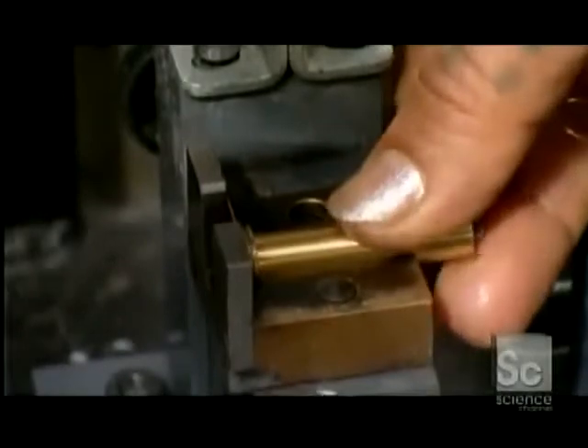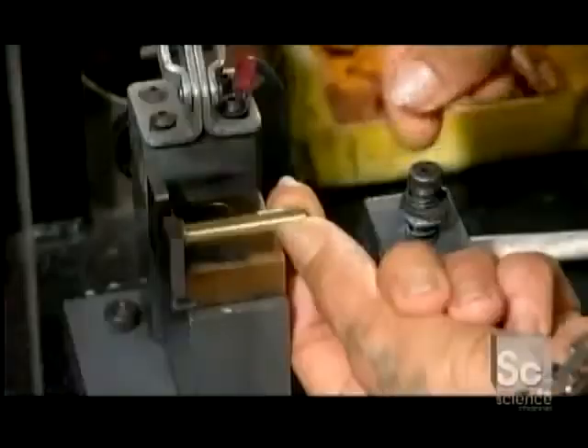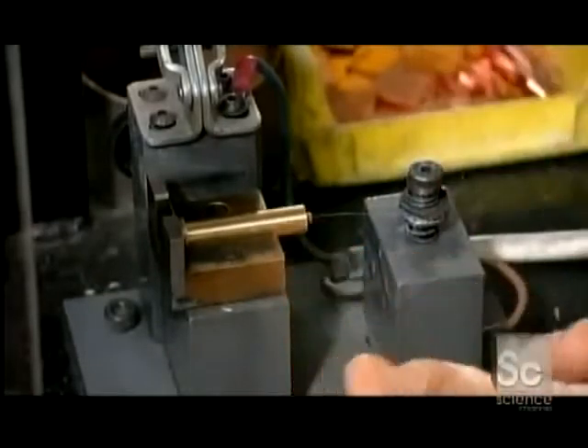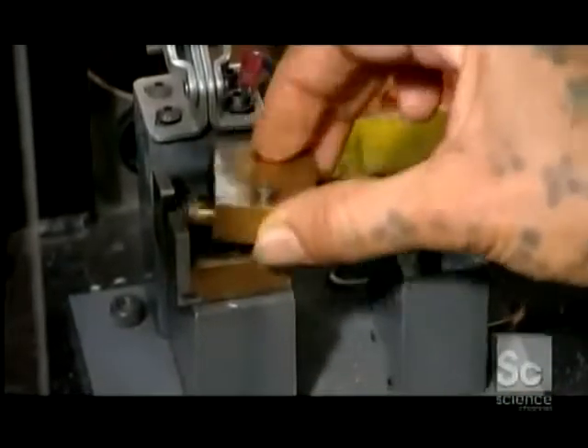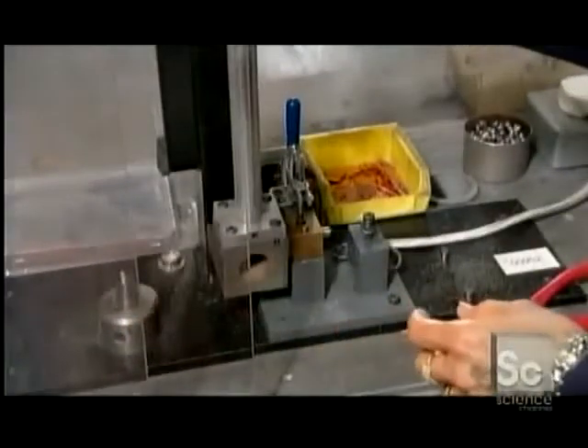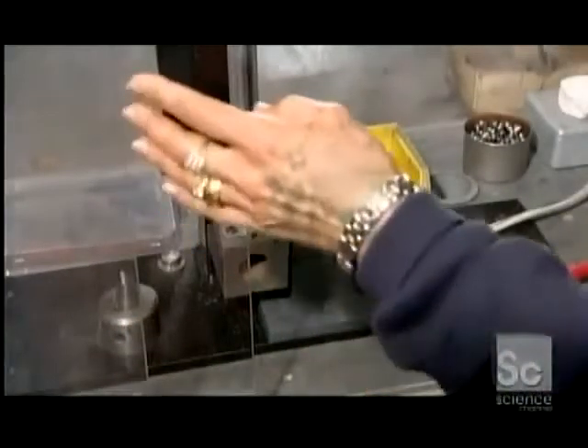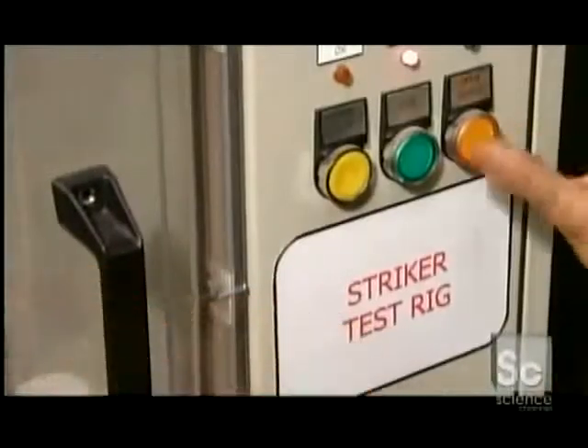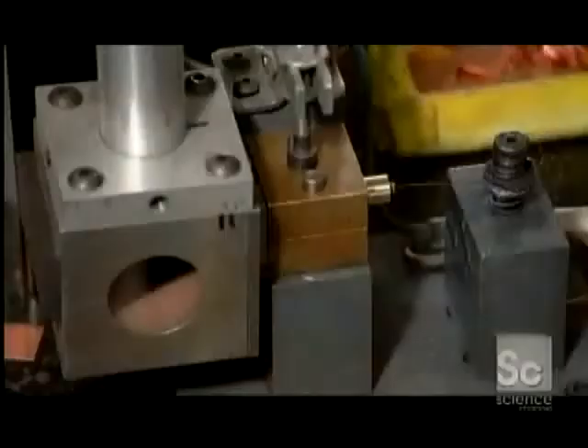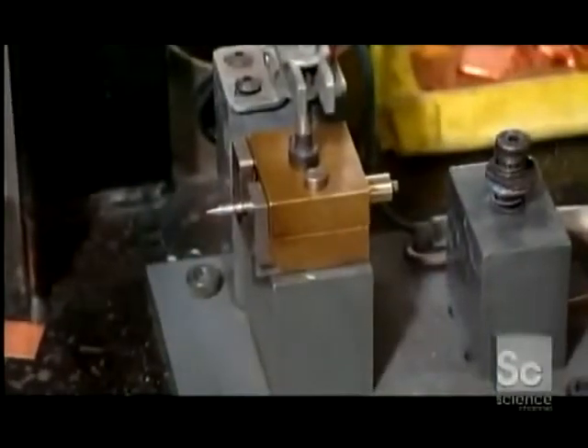This test run shows how it all happens. The pin's ignition wire is wrapped around an electrical post. Workers clamp down the pin and position the pendulum that swings to indicate the amount of force with which the pin fires. A jolt of power detonates the explosive, causing the pin to protrude, signifying a blown fuse.